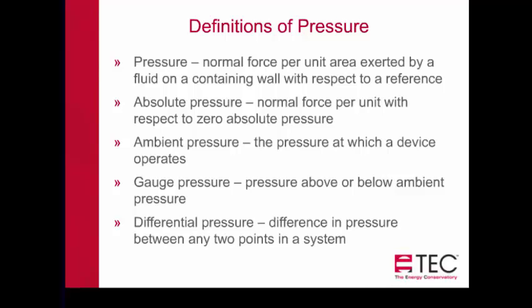Absolute pressure is a normal force per unit with respect to zero absolute pressure. Ambient pressure is the pressure at which a device operates — wherever you're at, that's the ambient pressure. Gauge pressure refers to measuring something above or below ambient; for example, tire pressure is read in PSIG — pressure with respect to the ambient area versus the inside of the tire. Differential pressure is simply the difference between any two points.